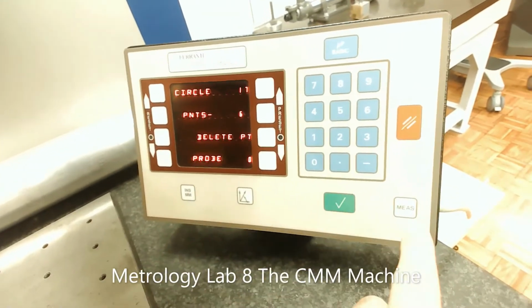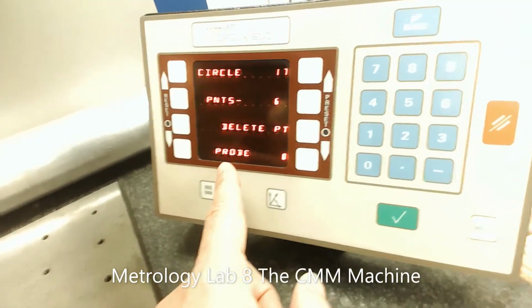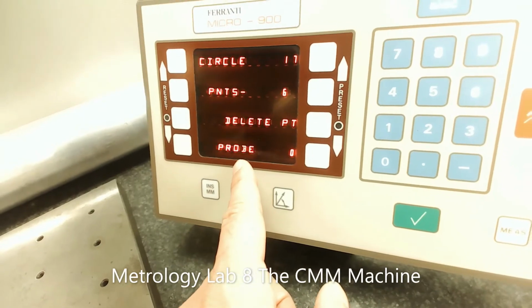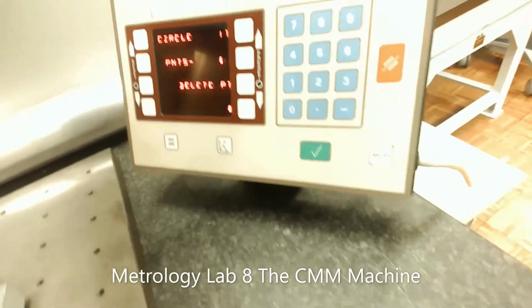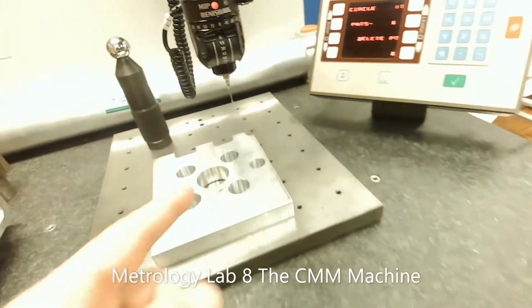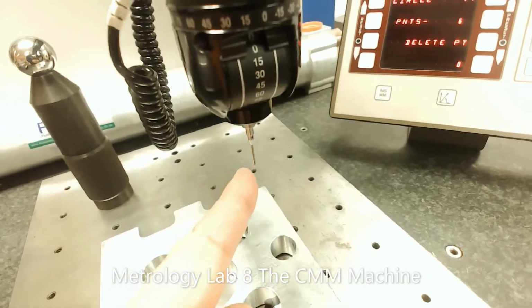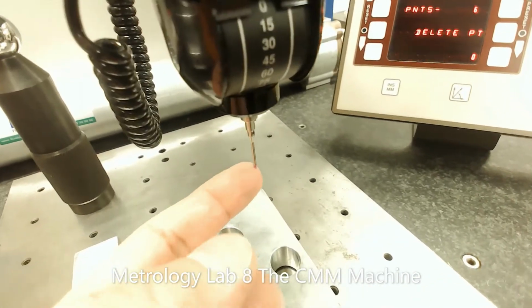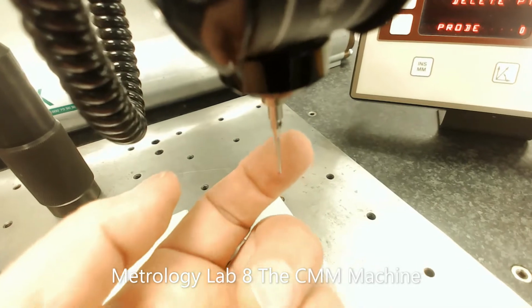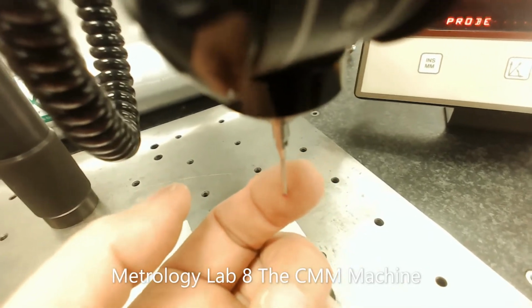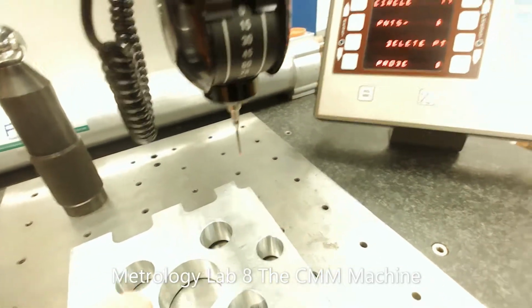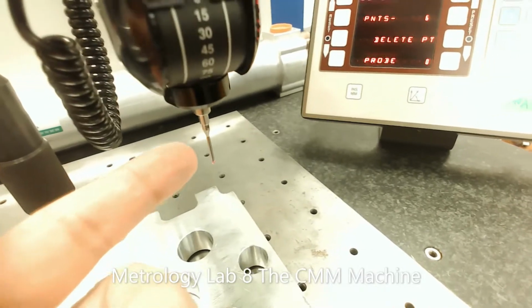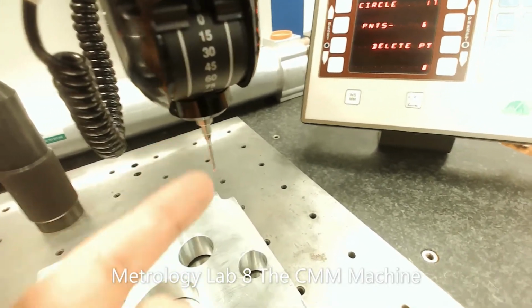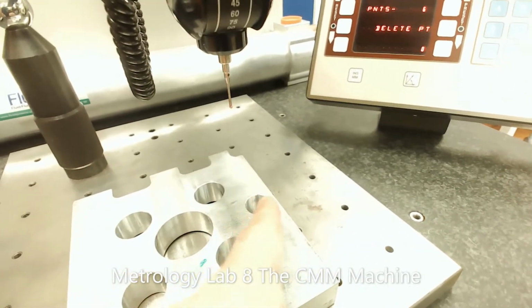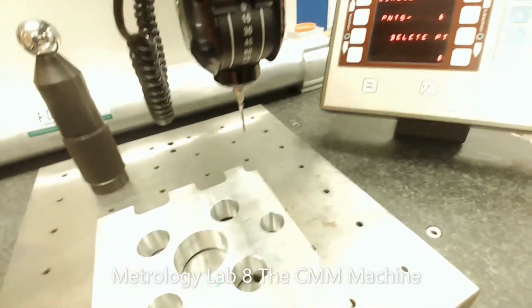As we press measurement, you can see that the probe starts flashing. That means the probe is ready to measure. This is the probe we have. This probe has a ruby sphere at the end. This ruby sphere is very sensitive. It's going to discharge the electrical current we have in this probe to the metal, to the part we're going to be in touch with.